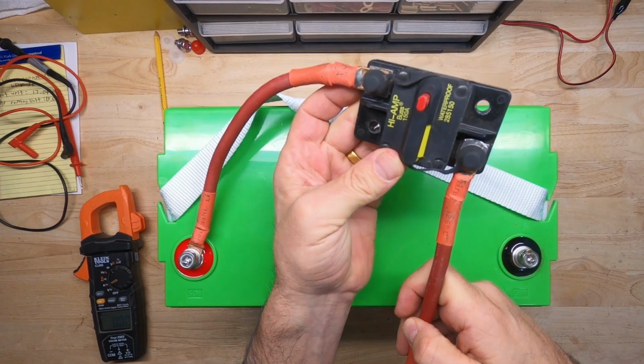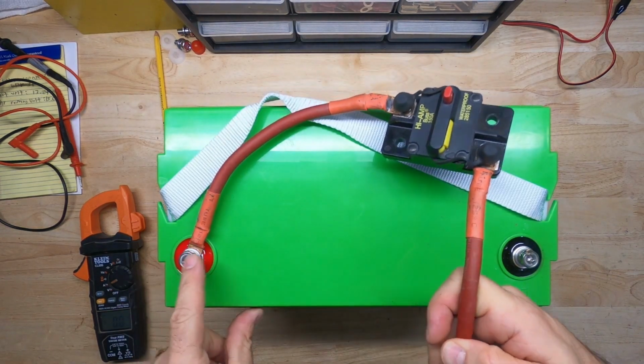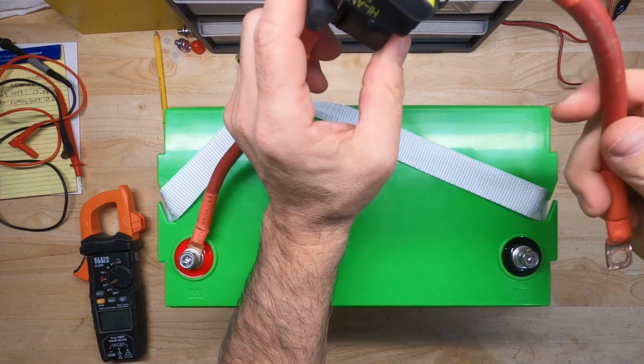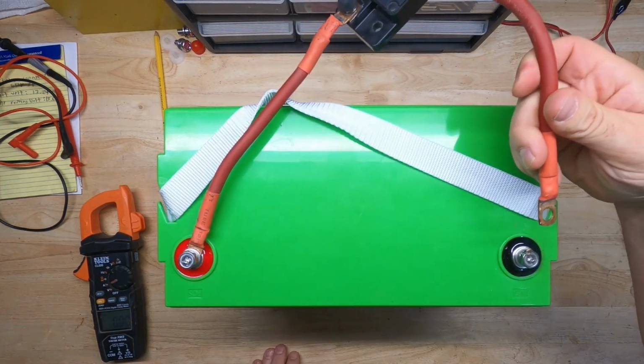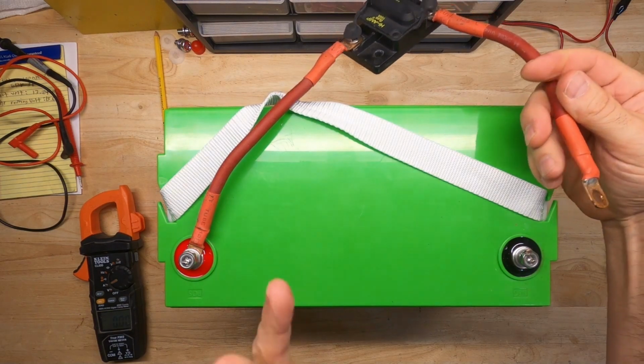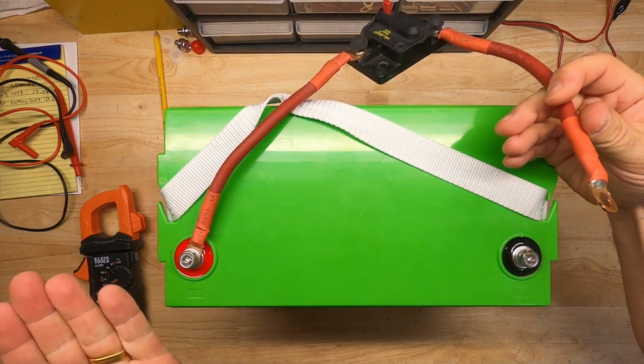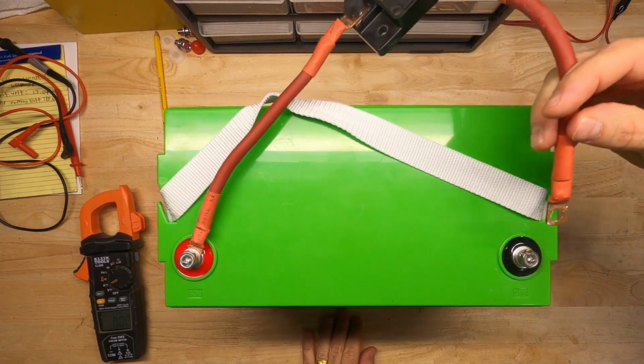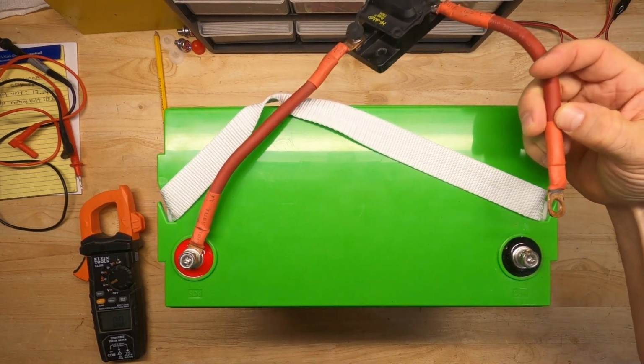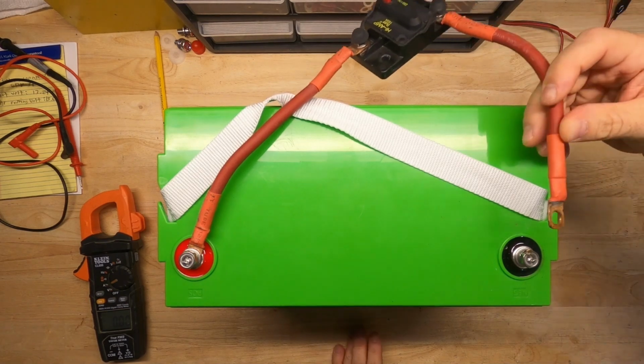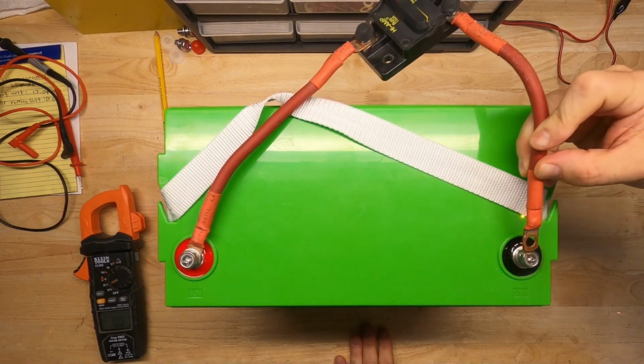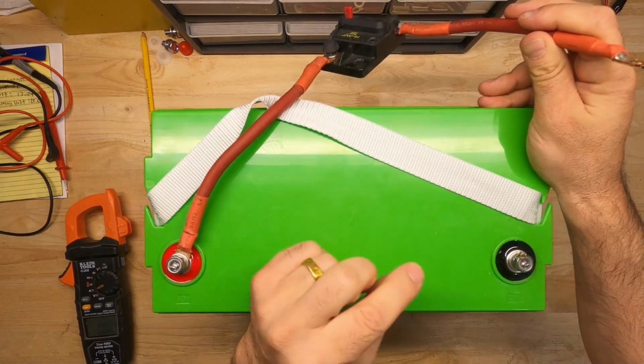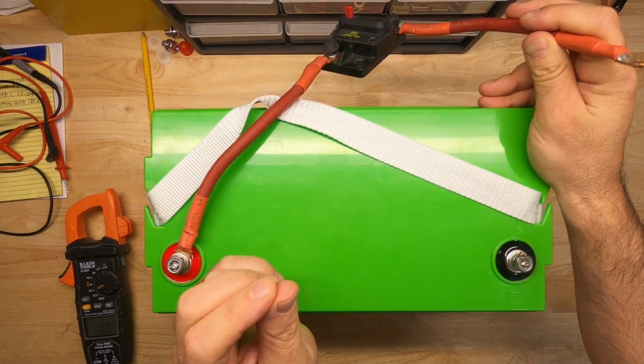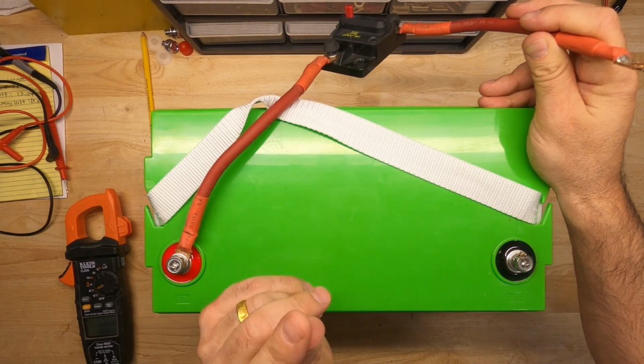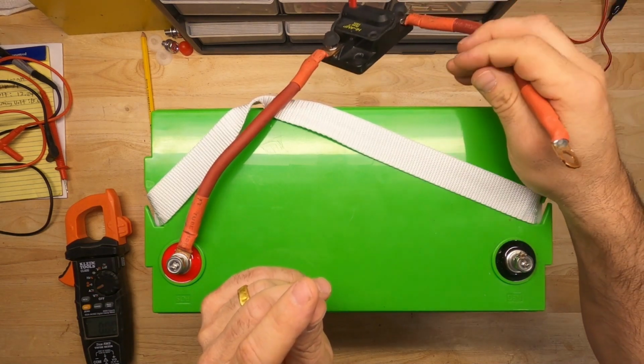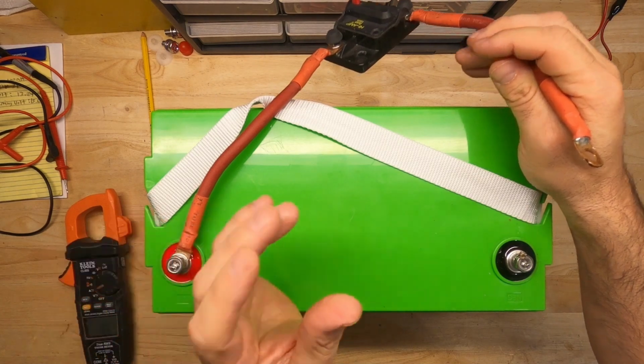Okay, so we're using a 150 amp breaker, and we're going to connect it directly from the positive to the negative. But before I connect this permanently, I'm going to do a quick jab on the negative terminal, just to show you what a short circuit could look like if you, say, dropped a tool on top of the terminals. Now it may not look like the BMS is doing anything, but it actually is. So you saw I jabbed it twice, and we got 2 sparks, so this BMS has a very quick recovery. So the next thing we're going to do is use the breaker, connect it up, and we're going to see exactly how fast that recovery is.